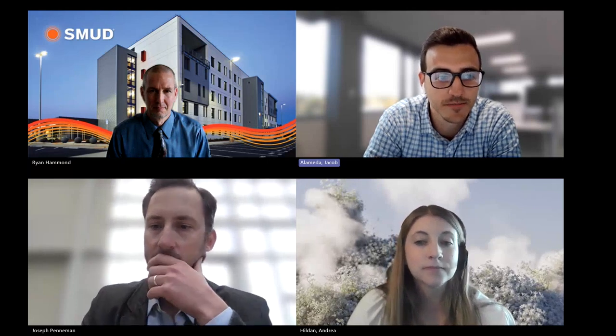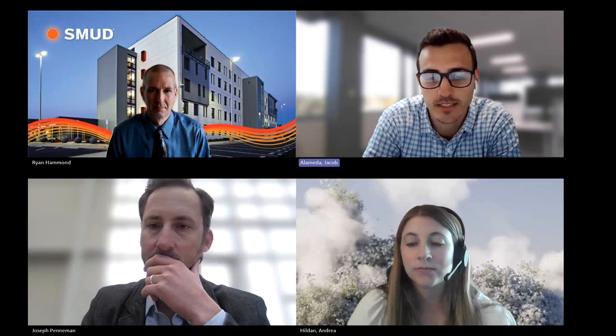Thank you. Yeah, I can take this one. So how reliable are these systems? I know that Glumac has done multiple emergency operations centers going into it with all electric systems for new builds. So I would say customers are very comfortable with using these as reliable systems. And they do that through providing redundancy and backup equipment. You can think of it a lot like a chilled water system. So just like you would have redundant chillers and backup chillers and lead lag systems in place, you can use that approach. So you'd have heating hot water pumps, N+1 pumps. You'd have N+1 chillers, or heat pumps in this case for your heating systems.